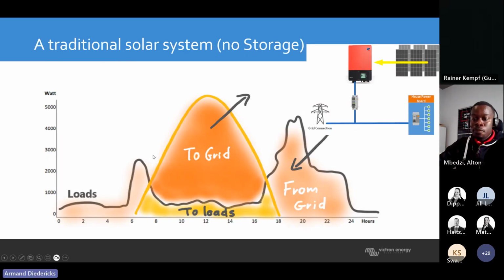All right. So this is just explaining ESS, a traditional solar system, no storage, just on a grid tie. So the primary function on a grid tie system is to do peak shaving. Most of the clients that didn't have load shedding as such did grid tie systems and did peak shaving. But now, with load shedding being so active and being on stage 6, most of the clients phone and say, listen, we have a grid tie system, we do have solar, what can we do to run partially off grid during daylight?